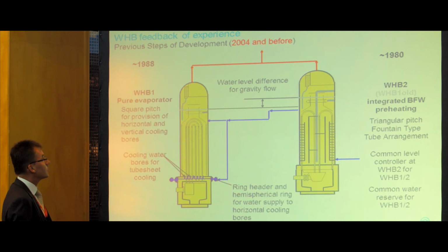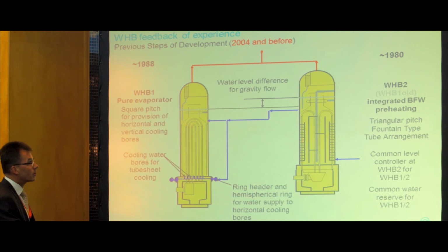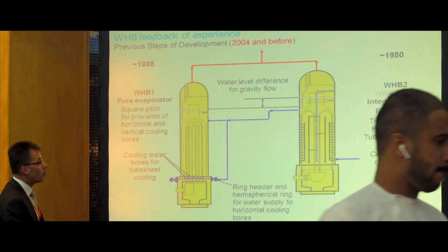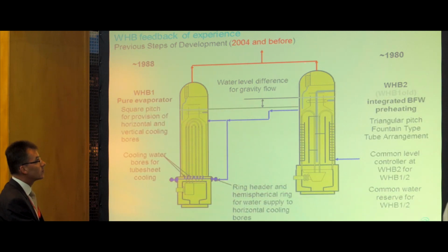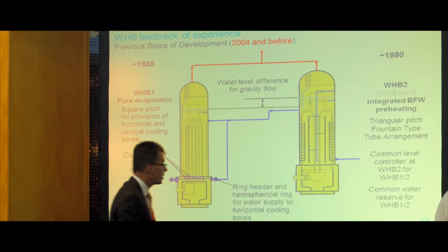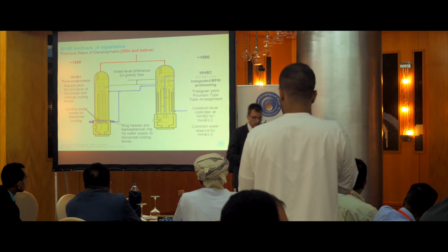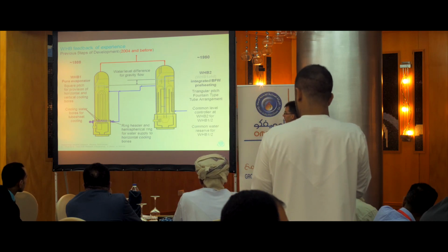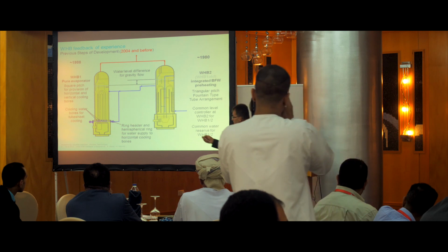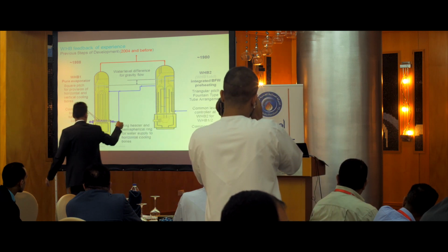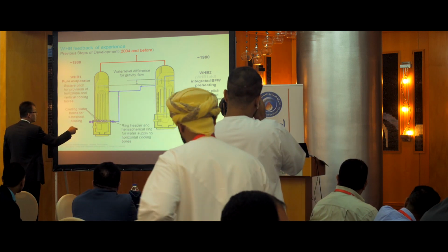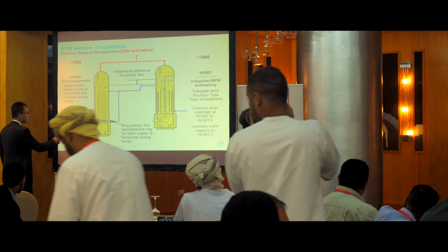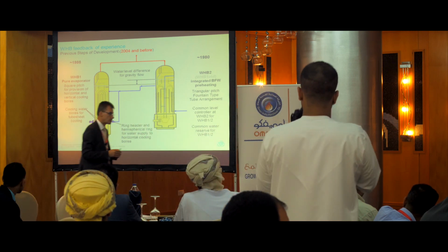With the two-converter concept, this boiler changed a little bit, because now only 20% have been used to produce steam. 80% just goes to the other waste heat boiler. And mainly, not what everyone thinks, up here in the waste heat boiler, most of the water goes in through the cooling bores.